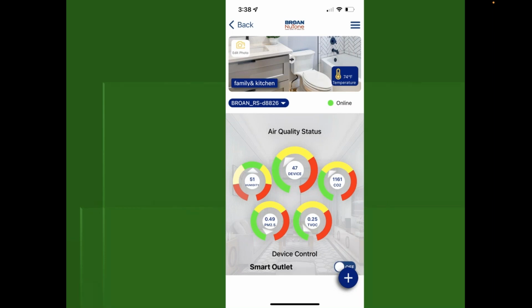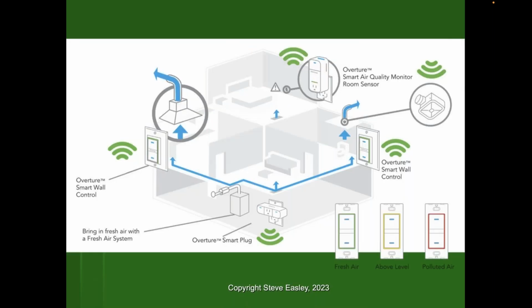So if I don't have an indoor air quality problem, I'm not over ventilating my house. And that's the beauty of these types of systems. They can control my range hood, they can control my ERV. I can have individual switches in each room which will monitor the indoor air quality and let me know if I've got polluted air, it's red, or if it's above levels, it's yellow, or if everything's good, it's green. These systems are really clever in their ability to monitor indoor air quality. And the reason I like this is that I'm not paying to overventilate my house when my indoor air quality doesn't require it.